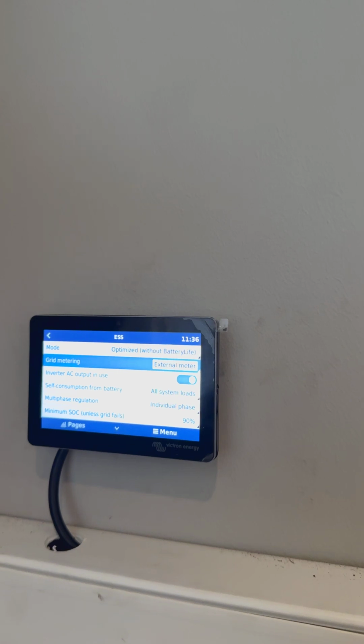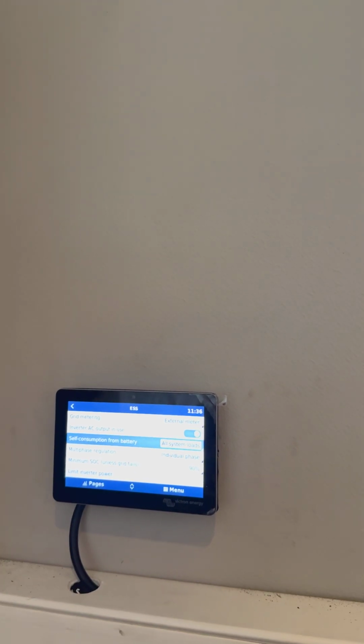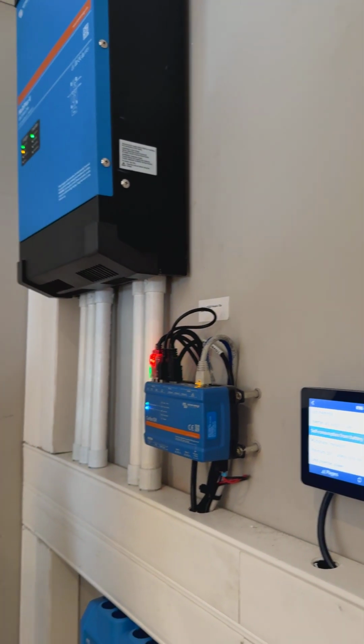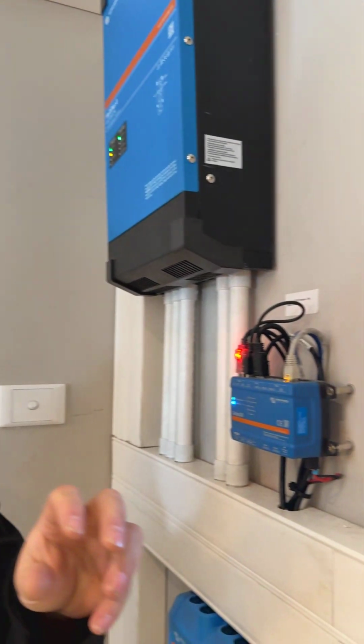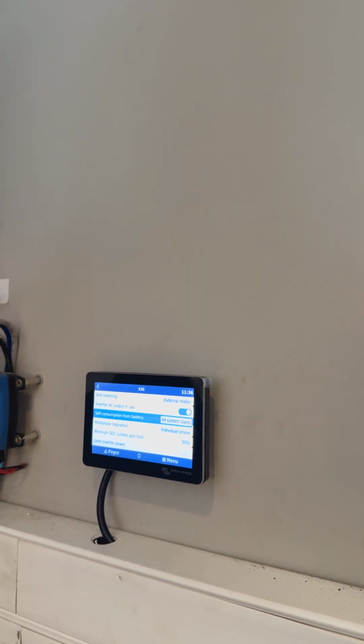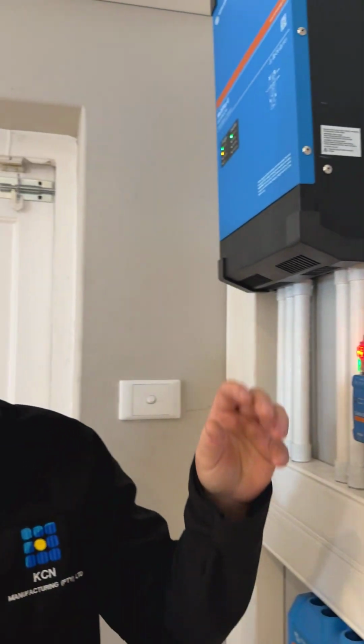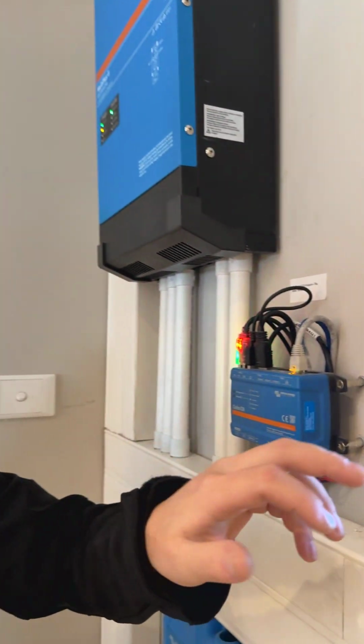If you do use your energy meter, your inverter AC output in use should, in most cases, always be on. If you switch that off, your solar will not feed to the AC output of your inverter, so it will block that load. Make sure that setting is on.